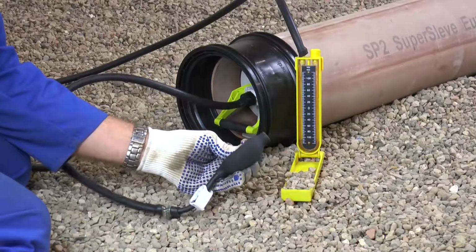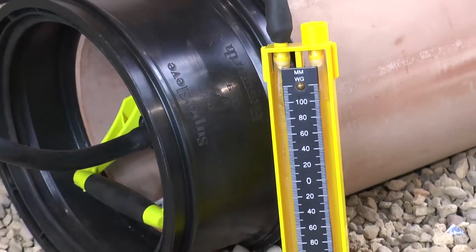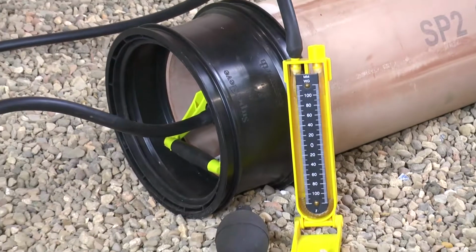Does the manometer or water gauge have water in it to the correct level? It is easily knocked over and can lose the water inside, which may not be readily noticed.